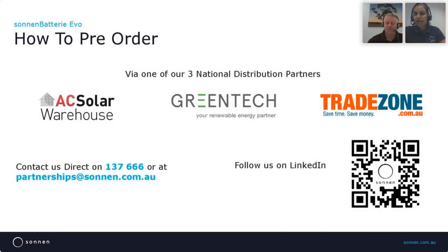Gary asked, will it recharge in a blackout with an AC solar system? The answer to that is yes. There are two ways it will do that. If the battery still has capacity, it will automatically send a grid reference to the AC coupled inverter to create that microgrid, then discharge to cover the loads, and will also use any available PV to help supply that load and charge the battery. If the battery is fully depleted, once there is available solar, we can press the black start button on the side to send that grid reference to the AC coupled inverter, and it will create its own mini grid again, supplying that designated circuit using the PV solar generation as well as charging the battery.